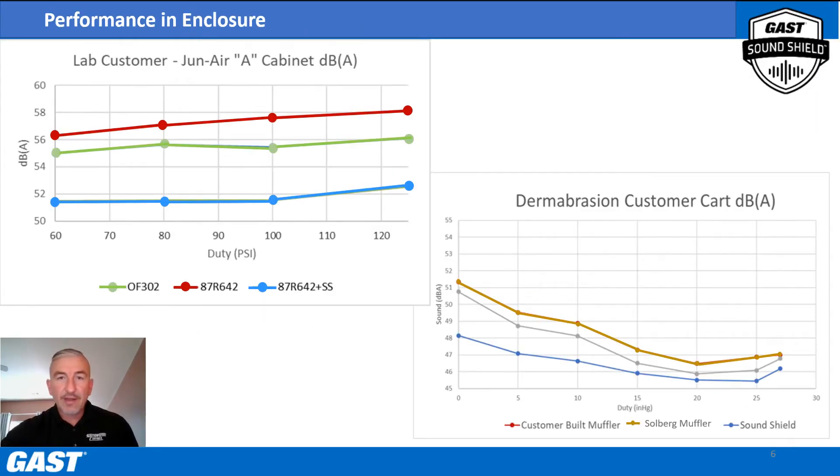Here we have two three-way comparisons. The upper left chart lists decibel levels of an 87R in red compared to a Jun-Air OF302, a common compressor used in labs, in green, and the SoundShield-equipped 87R in blue. The lower right chart shows a dermabrasion machine with a customer-built muffler in brown, a Solberg high-performance muffler in gray, and the SoundShield-equipped dermabrasion machine with no muffler in blue. As you can see, sound levels are significantly lower in both charts with the SoundShield-equipped compressor.